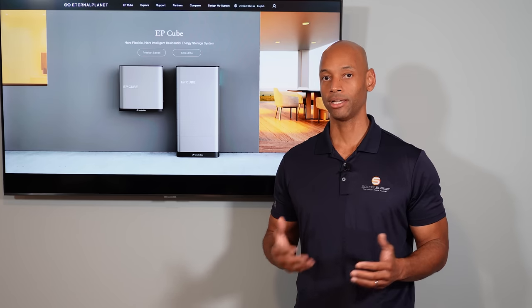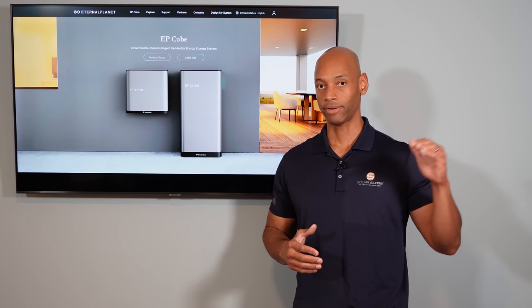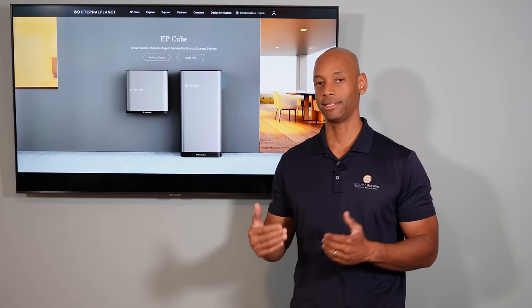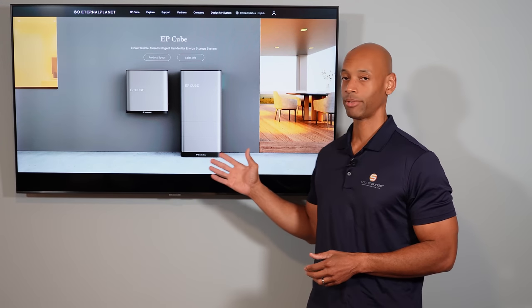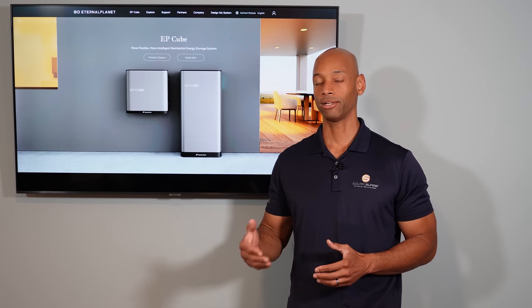You can also take advantage of the efficiency of a DC coupled solar power system if you're doing a brand new installation of your solar and storage at the same time. DC to DC solar-to-battery charging is more efficient than when you have to convert from DC to AC and then back to DC to charge into the battery. So with the EP-Cube system you basically have the best of both worlds — AC coupling for retrofitting batteries after the fact, or DC coupling for a clean, efficient initial solar and storage installation.